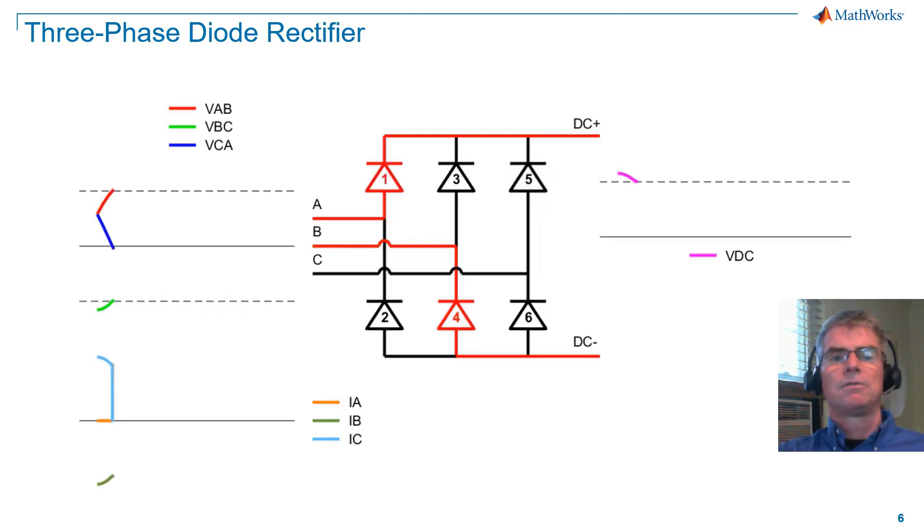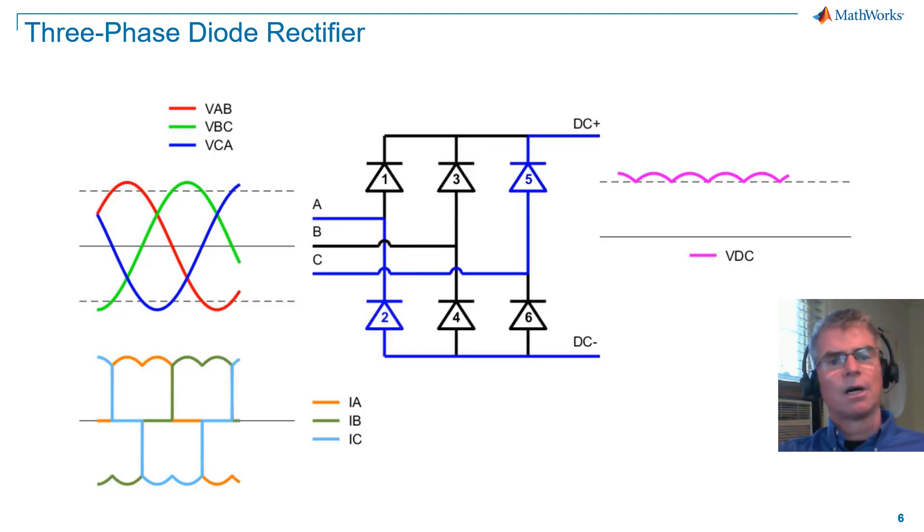Our final observation on the six-pulse rectifier is the effect it has on the AC current. On the bottom left, you can see that line current is not a sinusoid. The commutation has caused the line current to be contaminated with harmonics. That is, frequency components that are higher than the supply frequency. We'll cover harmonic analysis in a future tutorial.